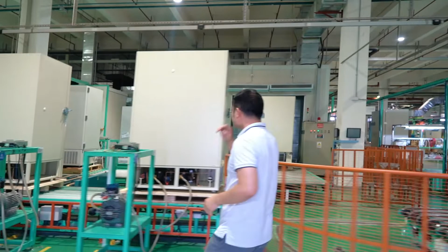After the installation, we will do the vacuum. The pressure for the equipment is also a critical issue for the refrigeration system, so we have to make sure the pressure is perfectly working. Thanks to this vacuum pipe, we will not stop this vacuum process unless the high and low pressure achieves about 15 pascals.